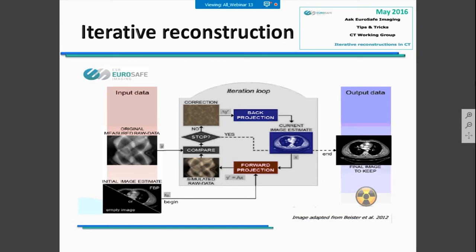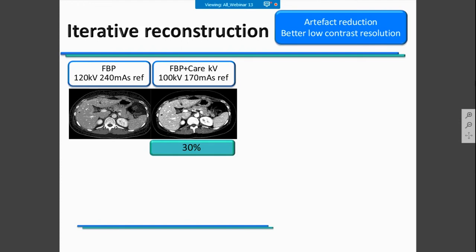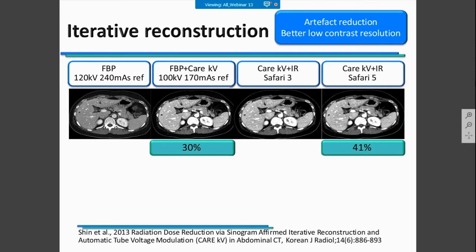If you want more information about iterative reconstruction, you also have a report from the CT working group available on the EuroSafe website. Iterative reconstruction allows you to have artifact reduction and also better low-contrast resolution. However, using iterative reconstruction is sometimes challenging at the beginning and requires specific training. For example, if you compare having filtered back projection and then switching to tube current and voltage modulation, you could obtain a 30% dose reduction. But if you also have iterative reconstruction available, you could further reduce the dose you already achieved.